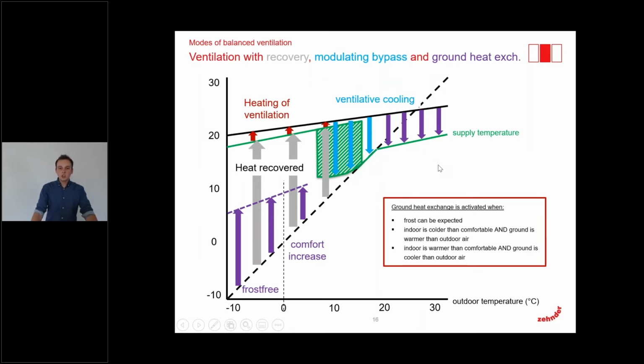Now we have additionally a ground heat exchanger. And what you can see here at low temperatures, when we are at minus degrees, is that we are preheating the outdoor air to protect the unit from freezing. So we have a frost protection. When it's still cold but warmer than 0 degrees, we have a comfort increase because we are pre-tempering the outdoor air, so we get a higher efficiency. And in summer, when it's warm outside, we are pre-cooling the air, and there we can make use of ventilative cooling using our ground heat exchanger. So here we also have energy savings.